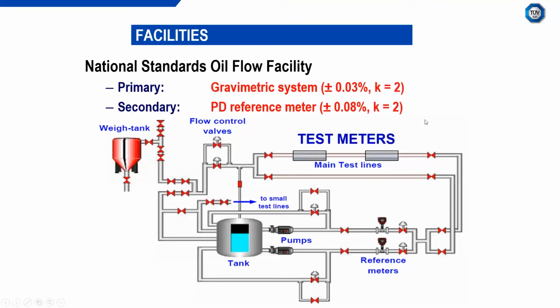And when we use high viscosity fluids, and that's termed anything greater than 30 centistoke, the uncertainty is 0.15% at K equals 2. And that's the same for both the gravimetric system and the PDs. However, for calibrating a Coriolis directly against our gravimetric system, the uncertainty is actually 0.05%.